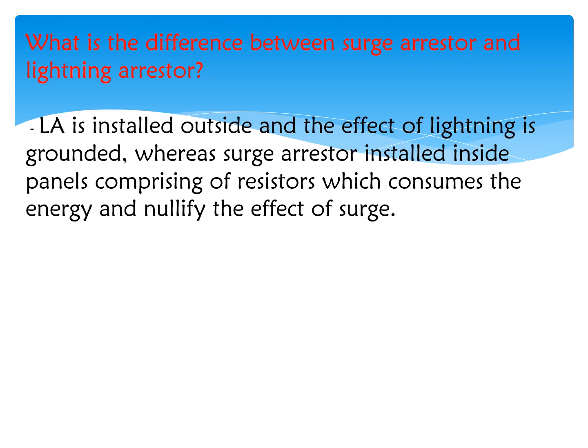What is the difference between surge arrestor and lightning arrestor? Lightning arrestors are installed outside and the effect of lightning is grounded, whereas surge arrestors are installed inside the panel, comprising resistors which consume the energy and nullify the effect of surge.